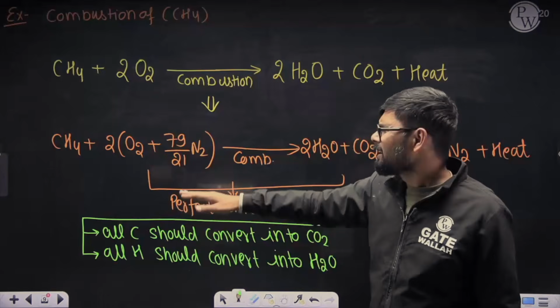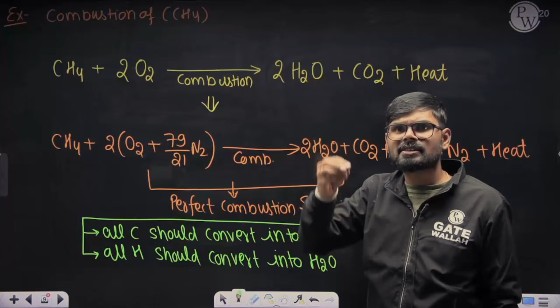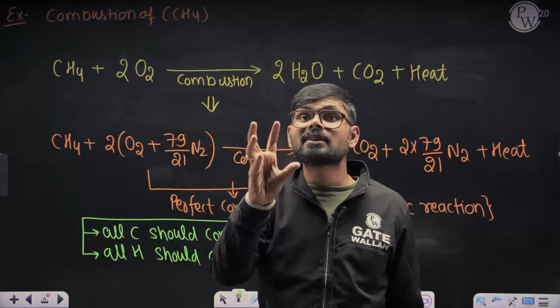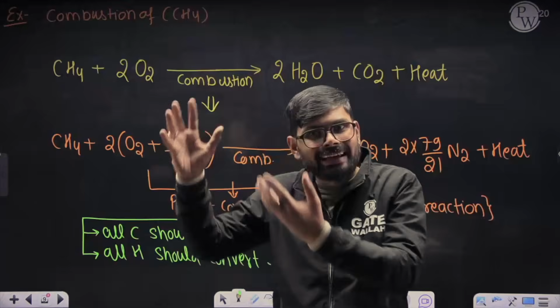Fine. And one more thing, another person may do that, okay, sir, put here more oxygen, sir, more air supply, sir. Here, 2 times of this required, you supply 3 times, sir. What is the problem? Combustion will be complete only, but that is not perfect combustion. Why? Because if you are supplying extra air, that extra air will also take some amount of energy and go out as air only. Let's say 2 kg air is required for combustion. You are supplying 3 kg. So 1 kg extra will do what? It will enter at 30 degrees centigrade and go out at 1000 degree temperature. So basically it will carry the heat and waste the heat, right?